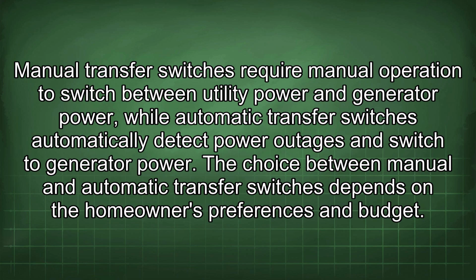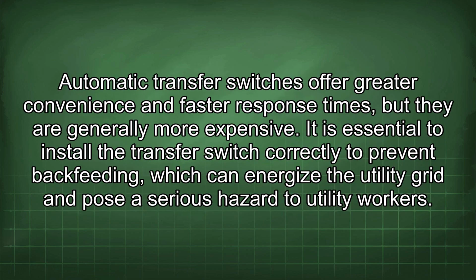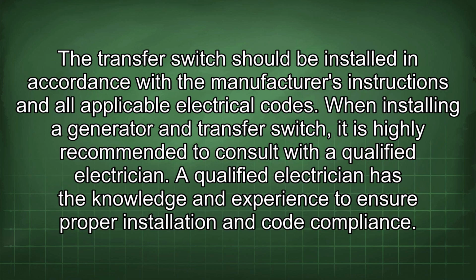The choice between manual and automatic transfer switches depends on the homeowner's preferences and budget. Automatic transfer switches offer greater convenience and faster response times, but they are generally more expensive. It is essential to install the transfer switch correctly to prevent backfeeding, which can energize the utility grid and pose a serious hazard to utility workers. The transfer switch should be installed in accordance with the manufacturer's instructions and all applicable electrical codes.